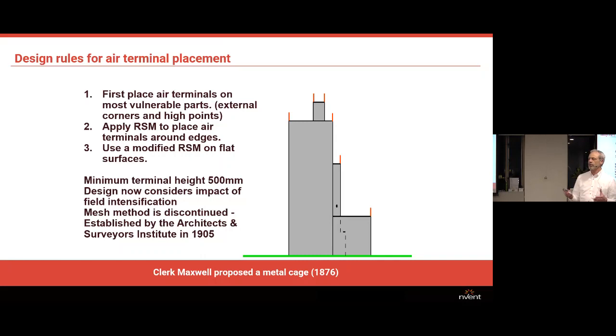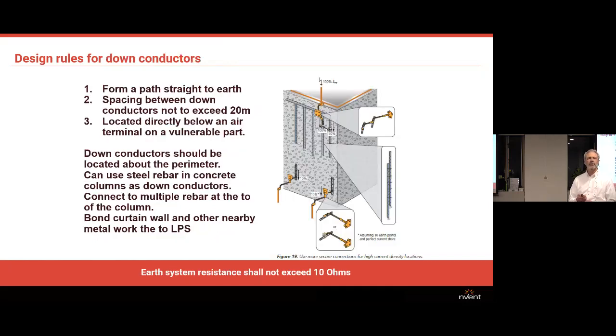This is the logical process for designing a direct strike conventional protection system. First, place your air terminals on the most vulnerable parts, which are the external corners and the high points, and then apply that rolling sphere method to place air terminals between them, or use those measurements in the previous table. In the flat surfaces between the edges, the standard allows that you can use the largest distances between the rods. And at the bottom of it tells you that that mesh method is discontinued. It was established by Architects and Surveyors Institute in 1905. They managed to get their influence in there because they don't like rods sticking up all over pretty buildings, and by putting in the flat conductors, you can't see them, but they are not so effective.